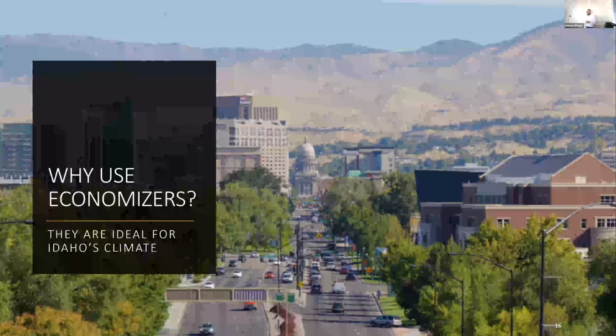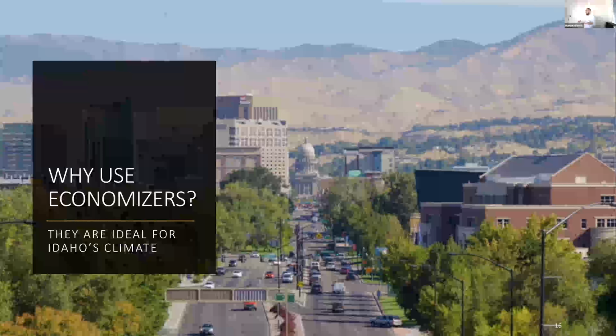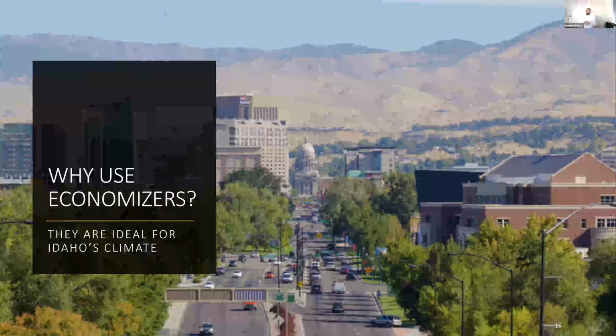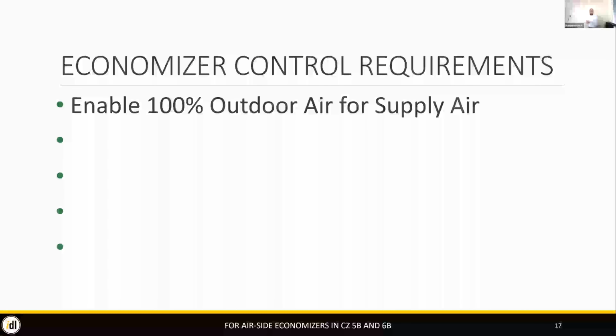But we found that by doing that, they would save about 50,000 kilowatt hours a year, which is about $4,000 in energy costs. And $4,000 isn't huge, but you think of the number of different commercial buildings in Idaho. If none of them had economizers, that adds up to a whole lot of money pretty quickly. You have 100 buildings like that, that's $400,000, right? And so that's why we have these requirements in the energy code. So this was kind of a cool example to see, oh, actually there's a reason to have these functioning in Idaho.